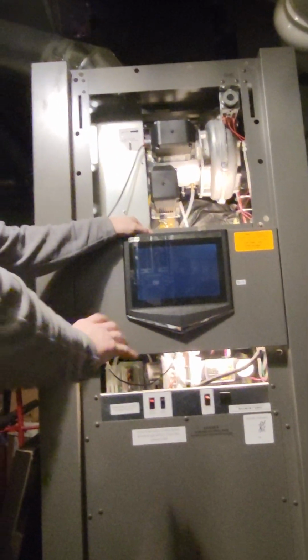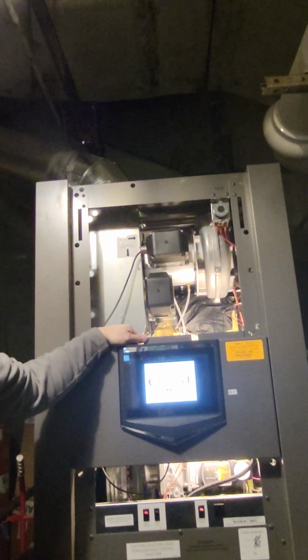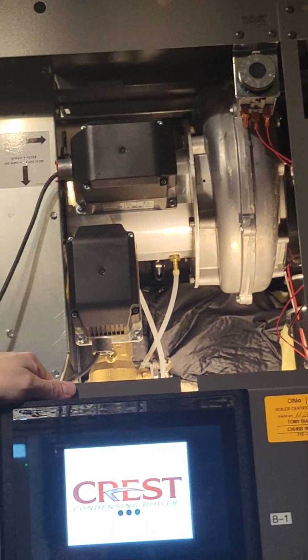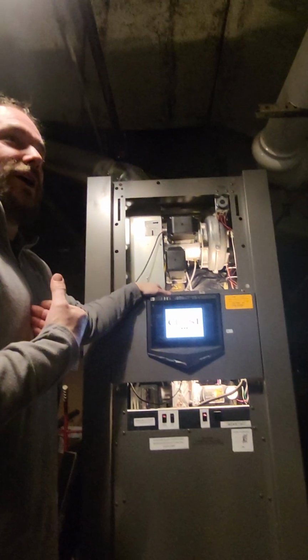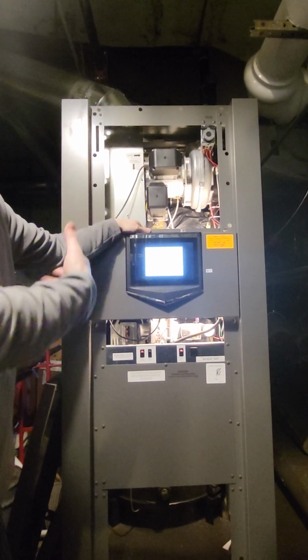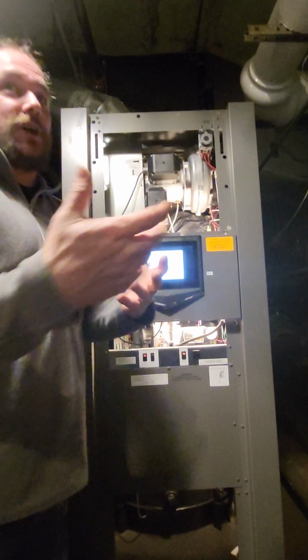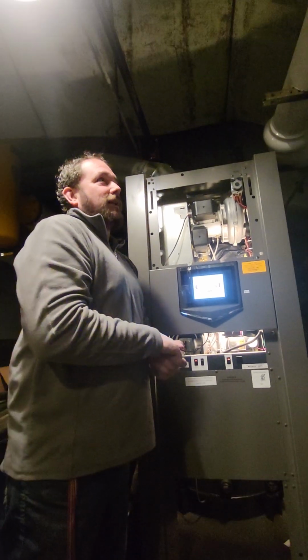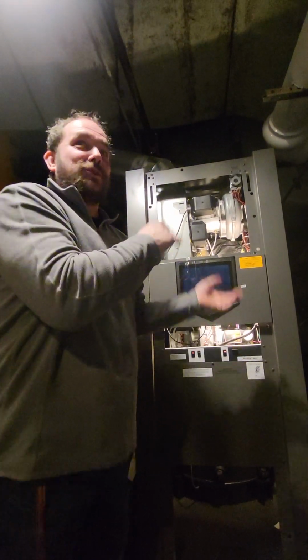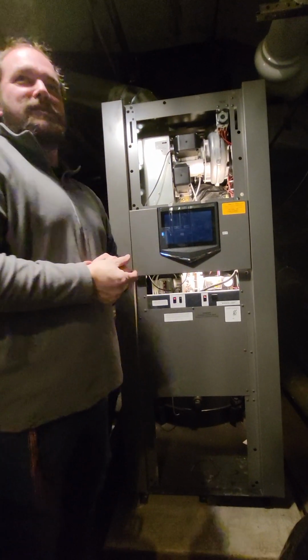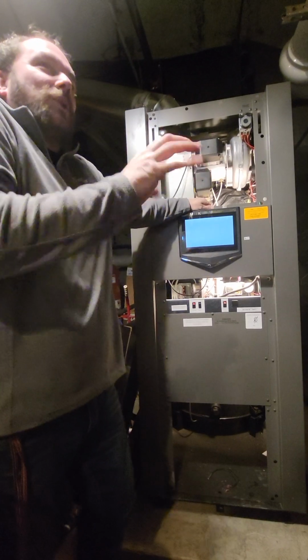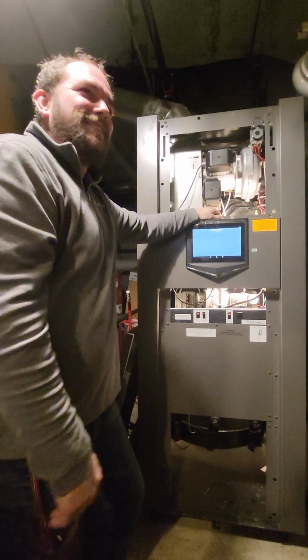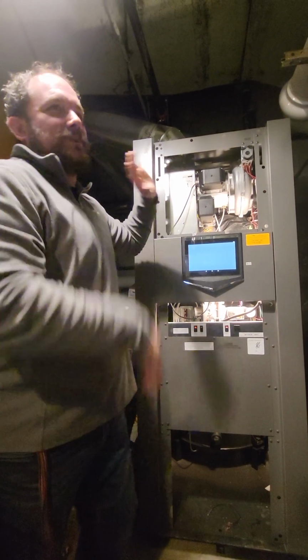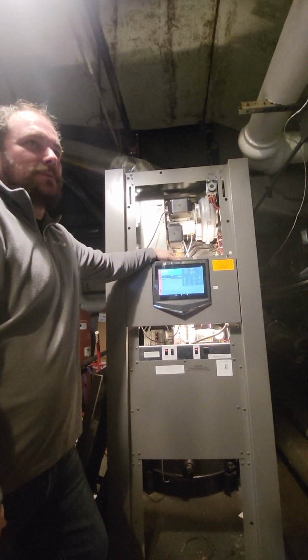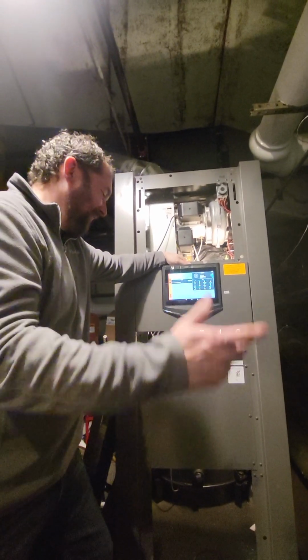We've had the Crest boiler for about, I believe, 13 years now. The Hellcat combustion system has been released for about 2 years now. We've had excellent success with them. They run really well. It's been great for us, especially me as the service guy doing startups. Like I was telling you before, we'll have jobs that run 365 days a year, and one could be tuned, did a startup in the winter and tuned for the winter, and then you get that call that you've got noise in the summertime when it's 95 degrees. But you don't really want to mess with it, because then you know it's not going to be right when it's 10 degrees outside and it gets cold. This combustion system takes all of that out of it. It's running at the same O2 all the time. You need a cool Hellcat logo, like around the Challenger. Yeah, that'd be badass. We told them that.